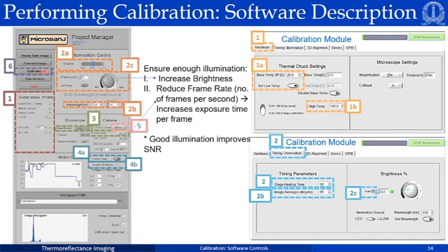Okay, so before we start the calibration, and when we start the tool, what are the things that we have to check? This will be described in detail in the demonstration session, but I will briefly highlight it right now so that during the demonstration you can understand it clearly. The moment you turn on your system, you have to look at the various communications. For example, is the software detecting your various synchronization timing modules? Is it detecting the CCD camera? Is it detecting the light sources, etc.? So you have to look for green lights corresponding to each module.